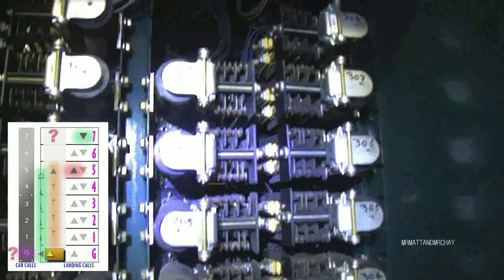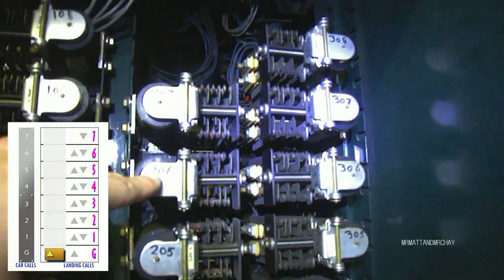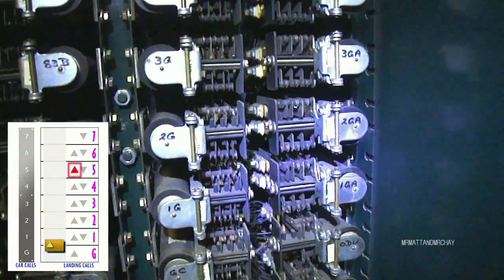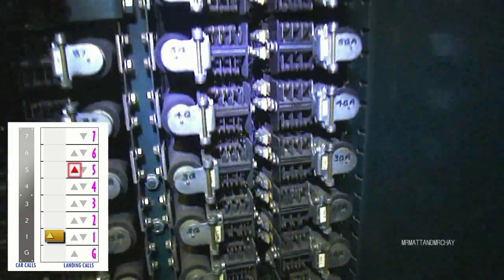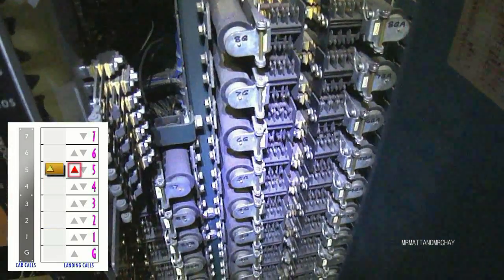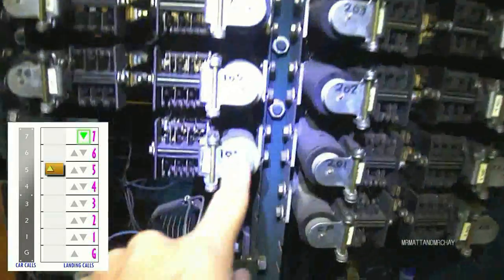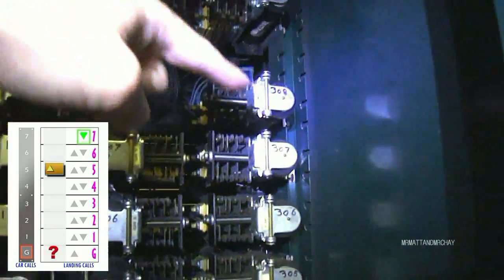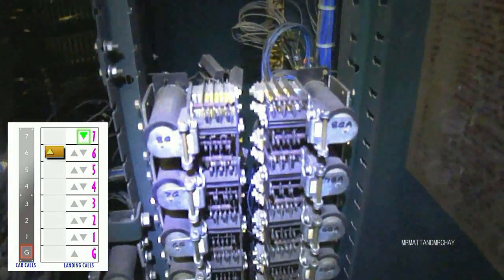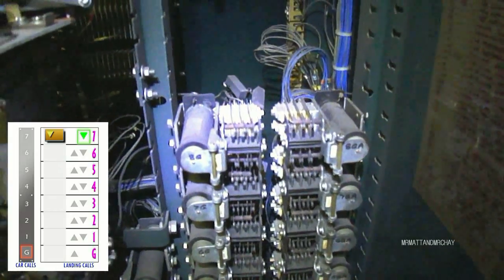Lift is on the ground floor. I'm going to press the up button on the fifth floor. The lift comes up. Going to give it a down button on the top floor, and then I'm going to press the ground button in the lift car. Now, as this was a collective state up, because I pressed the up button, will it now obey that one, or will it obey that one? Which way is it going to go? It's going to continue up. Cool.